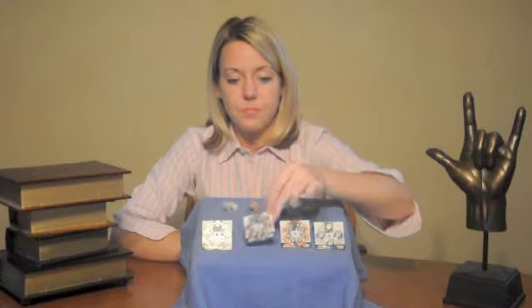Next are brown size 312. Once again, they're a little bit smaller and a little bit thinner. Finally, there's the smallest battery, size 10. It's easy to remember that the number and color go together. So just pick one, and when you go to purchase your batteries, remember that you're looking for the blue batteries. The bigger the battery, the longer it will last. You can expect your hearing aid battery to last anywhere from 1 week to 1 month, dependent upon the size and the use and duration that you're wearing your hearing aids per day.